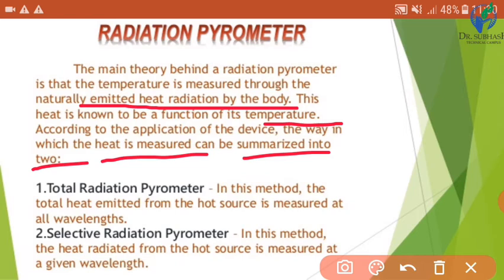Now, what is a total radiation pyrometer? In this method, the total heat emitted from the hot source is measured at all wavelengths. The total heat emitted from the hot source or hot body is measured at all wavelengths. It means all wavelengths are included in the total radiation pyrometer. Now the second one is the selective radiation pyrometer. As the name suggests, in this method the heat radiated from the hot source is measured at a given wavelength. So a particular selective range is there. The total range is not included, the total wavelength is not included in the selective radiation pyrometer.